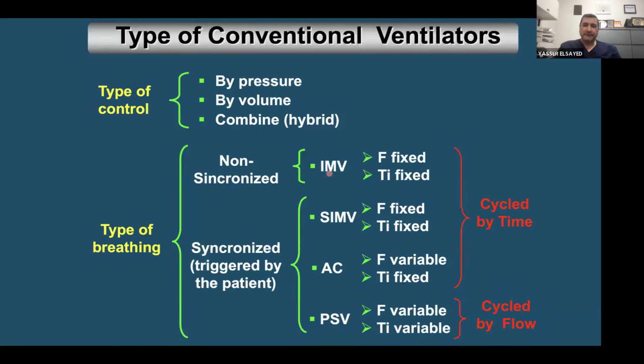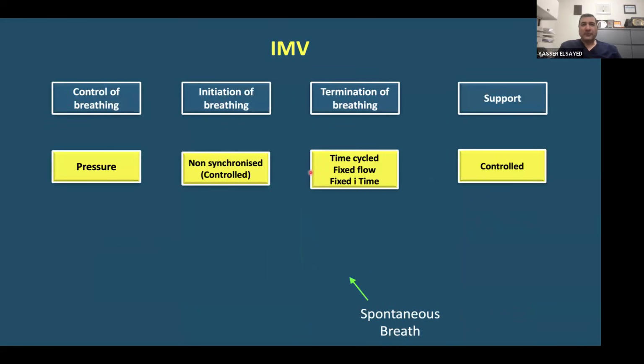So IMV, SIMV, AC, they are cycled by time because the I time is fixed. The inspiratory time is fixed for all of them. But PSV is cycled by flow because the I time is variable. The patients themselves decide the I time. So let us go one by one. IMV is the first mode used ever.